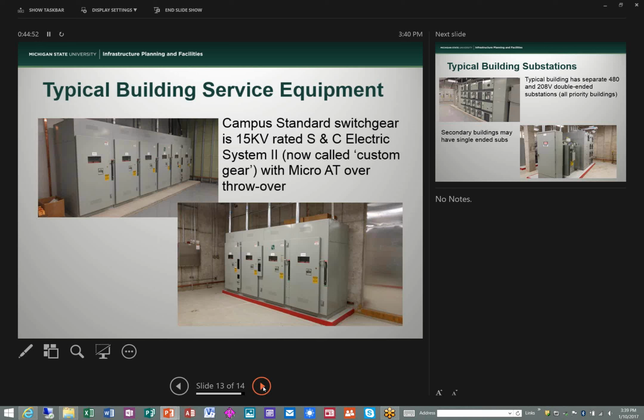65 of several hundred. But did the campus start islanded from the utility? I'm still a little surprised that the utility connection is only a fraction of what you are using on site. That's unique. Yeah, this is Bob, and your answer is yes. We built, I believe when the plant got built in 65, we put in 25 megawatts of generation in 65, and we put an 11 megawatt interconnection on the distribution for standby service. And it's always been a standby service connection with the local utility.